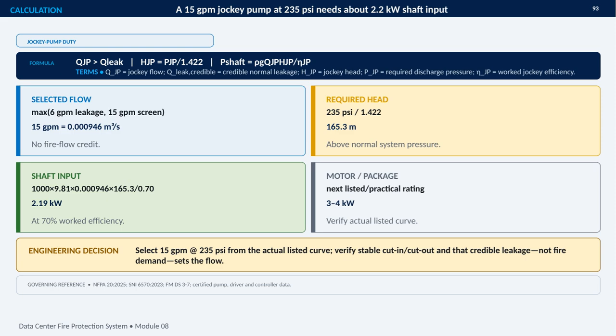The motor and package should therefore use the next practical listed rating, shown here as 3 to 4 kilowatts, but the final choice must be checked against the actual certified pump curve. We also need to verify stable cut-in and cut-out behavior. The governing principle is that credible leakage, not fire demand, sets jockey pump flow, consistent with the listed NFPA, SNI, FM, and certified equipment references.